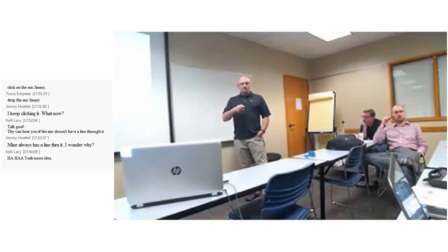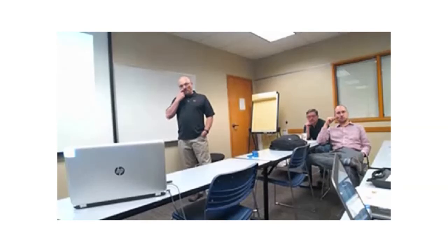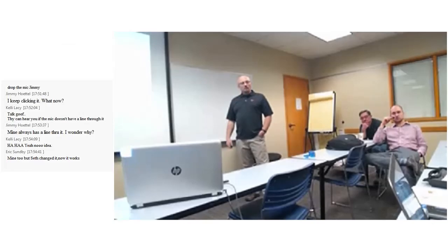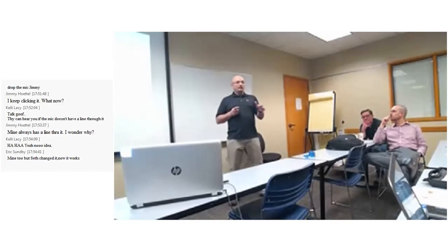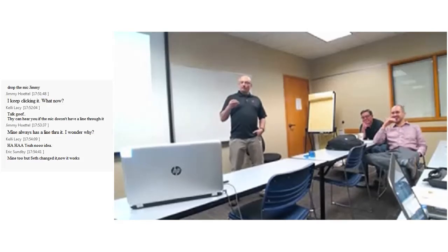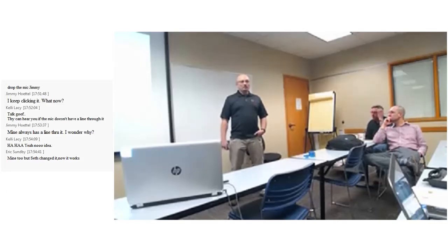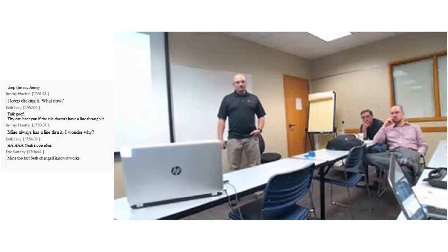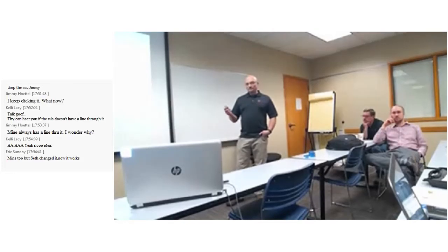But was there another question from Skype? Somebody asked if you could test a motor with that while it's hooked up to a speed drive, to a VFD. Oh, so no. Just like with your Megger, hopefully you guys are doing this, before you test it, you need to pull the leads off, because you don't want to take a chance of feeding back into the drive and damaging anything. Yeah. So, it doesn't usually, especially the size motors you guys are dealing with, it doesn't take very long to pull the 3 leads off, test it, and then hook it back up when you're done. Is that it? Yeah, I think so.